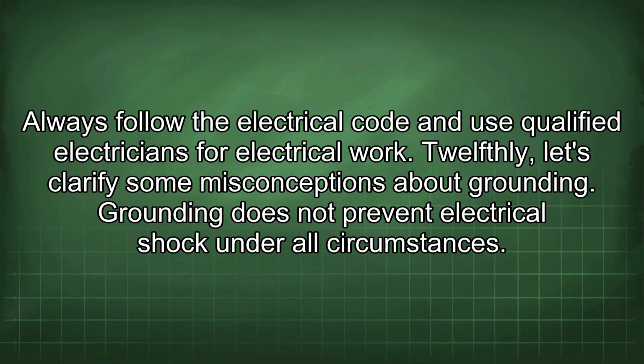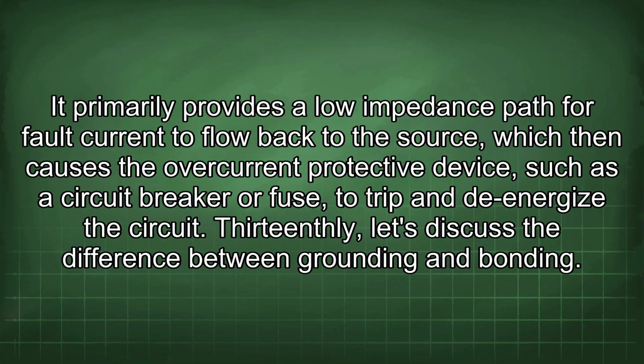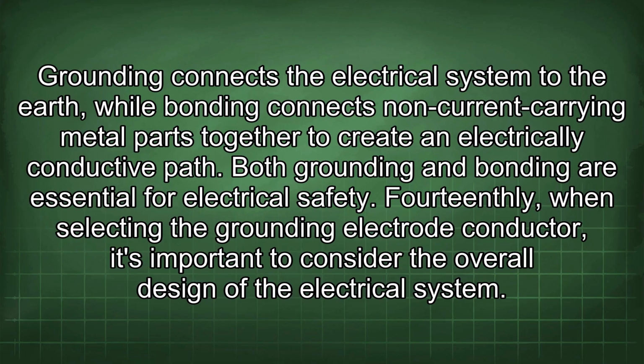Twelfthly, let's clarify some misconceptions about grounding. Grounding does not prevent electrical shock under all circumstances. It primarily provides a low impedance path for fault current to flow back to the source, which then causes the overcurrent protective device, such as a circuit breaker or fuse, to trip and de-energize the circuit. Thirteenthly, let's discuss the difference between grounding and bonding. Grounding connects the electrical system to the earth, while bonding connects non-current carrying metal parts together to create an electrically conductive path. Both grounding and bonding are essential for electrical safety.